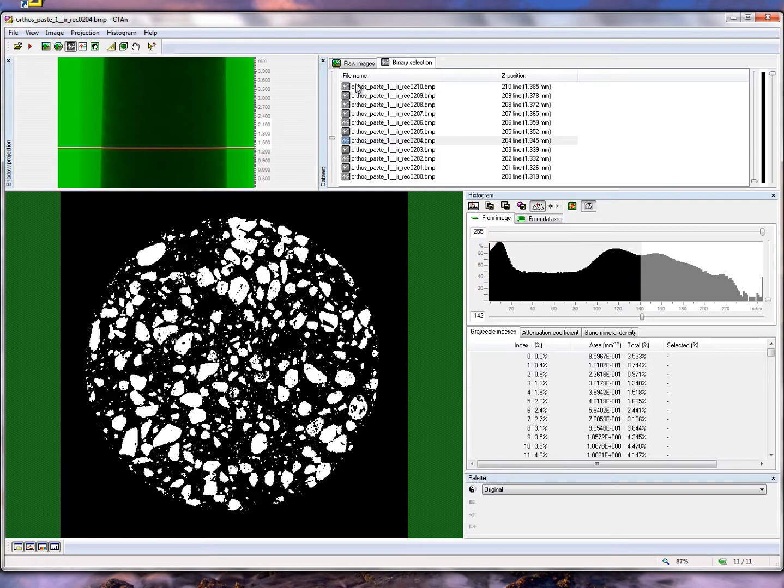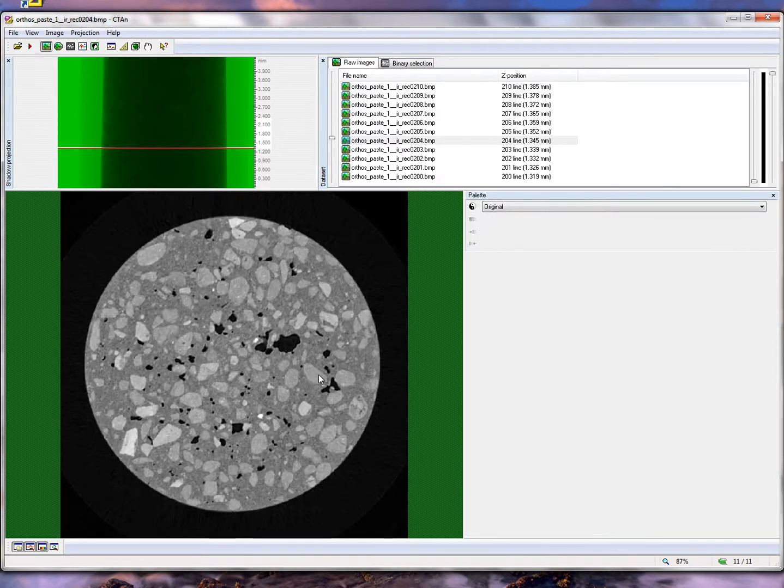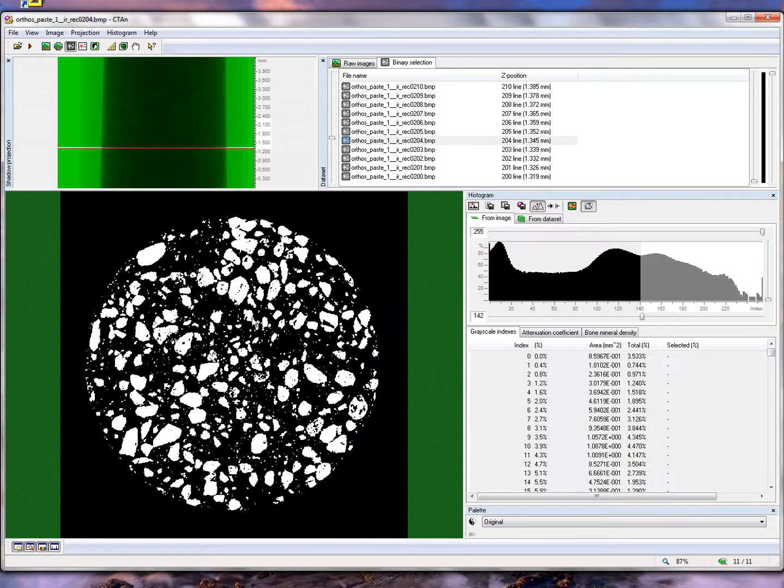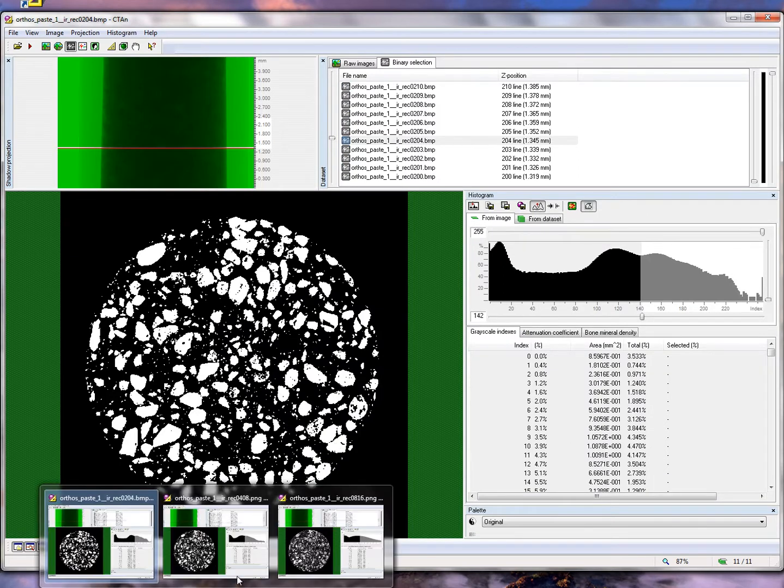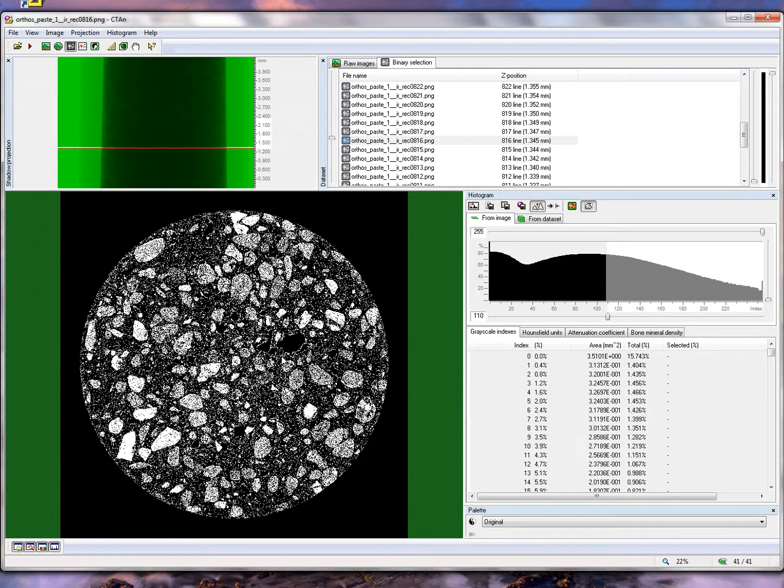This is the rationale for doing projection image resizing. It enables materials of a close density to be resolved more easily than they can at high resolution, where this process is complicated by noise.